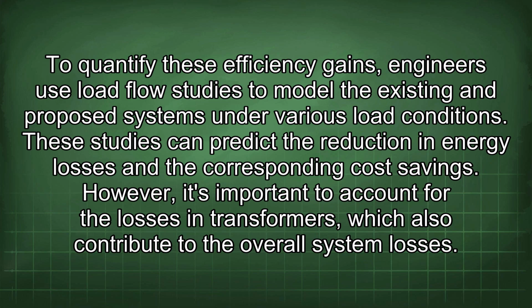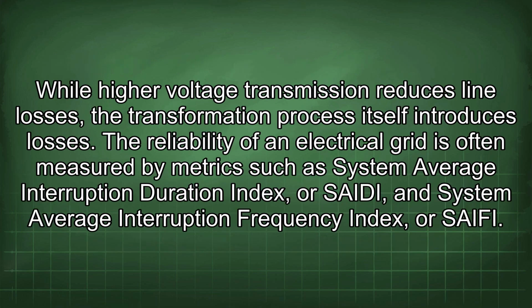To quantify these efficiency gains, engineers use load flow studies to model the existing and proposed systems under various load conditions. These studies can predict the reduction in energy losses and the corresponding cost savings. However, it's important to account for the losses in transformers, which also contribute to the overall system losses. While higher voltage transmission reduces line losses, the transformation process itself introduces losses.